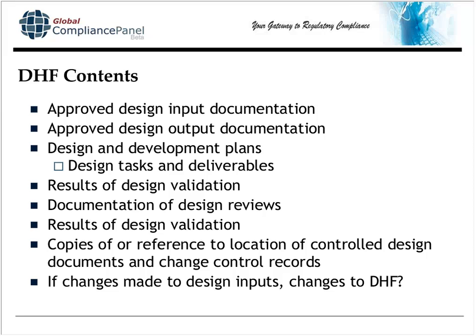The contents of the DHF begins with the design input documentation. During phase review of your design control process, you've got to have these design inputs approved. So at the end of the design input documentation, you'll have signatures — the signatures of the departments that your internal procedure requires, and the FDA inspector will look to make sure you met your own internal requirements. After the input documentation, which is what the device needs to do, is the output documentation, which shows that your device as designed and as manufactured meets the input requirements. I've seen many good matrices in my experience which link inputs to outputs, with each input having a specific reference to the validation or verification that shows a particular input requirement was met.